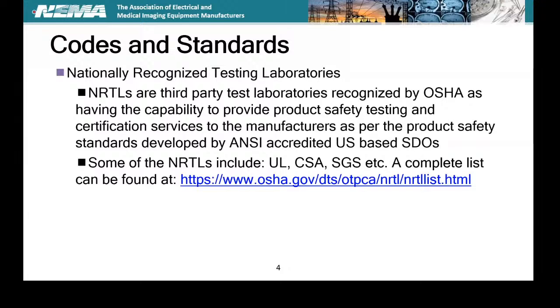If you go to the OSHA site and the NRTL program, you'll find that some NRTLs are limited in what they can test to. I'll give an example: they may only test light fixtures, luminaires, but that is under the auspices of OSHA. That's what they're granted. So not all NRTLs can test all products. There is a list of what they can test to on the site, which lists what is recognized by OSHA. If it's not on the list, it shouldn't be approved under the definition of approval in the NEC. Absolutely.